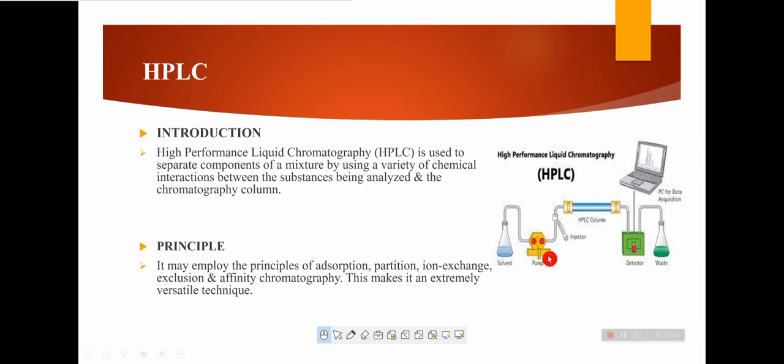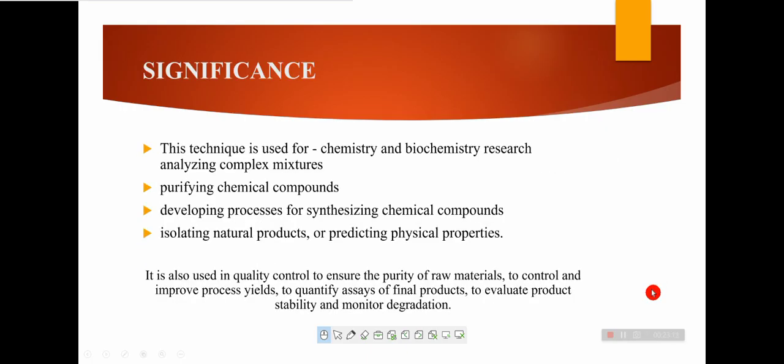or to the waste. In general, an HPLC system contains a solvent reservoir, a pump at high pressure, a constant speed through system to keep the drift and noise of the detector signal as low as possible. A constant and pulseless flow from the pump is crucial.